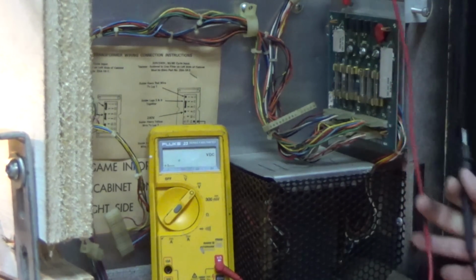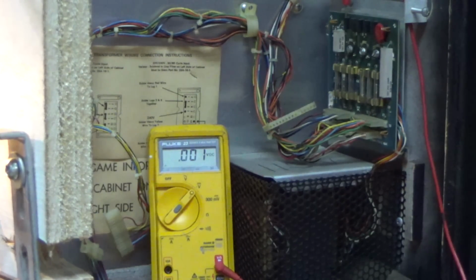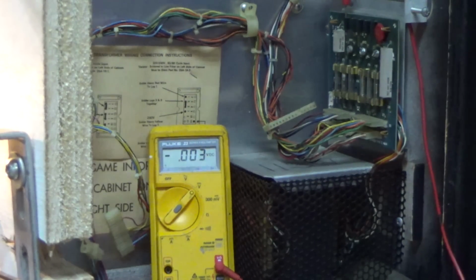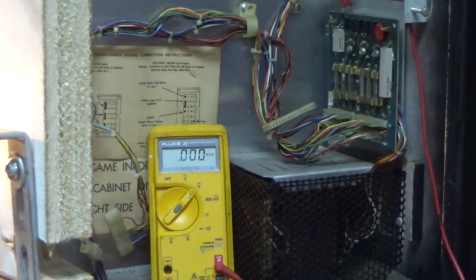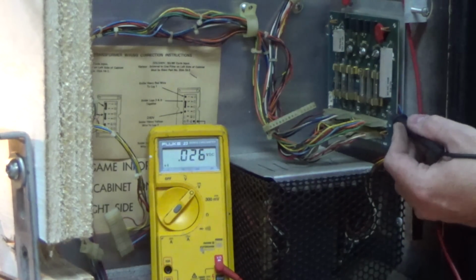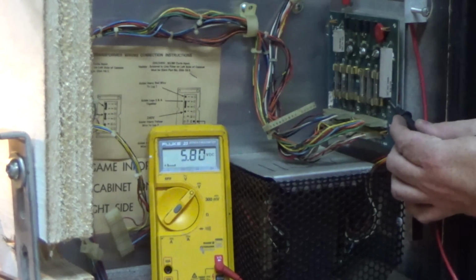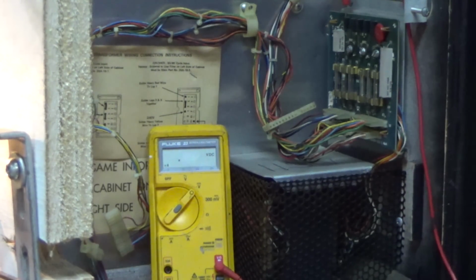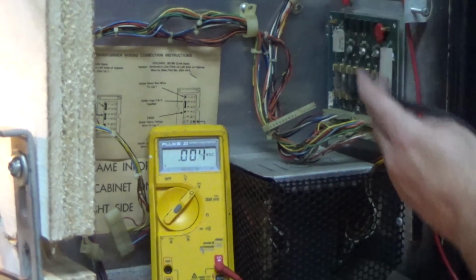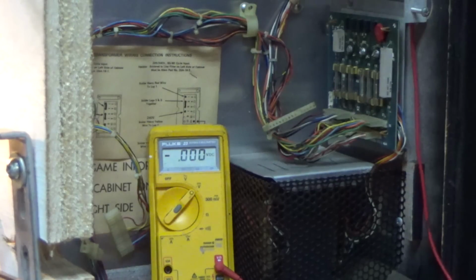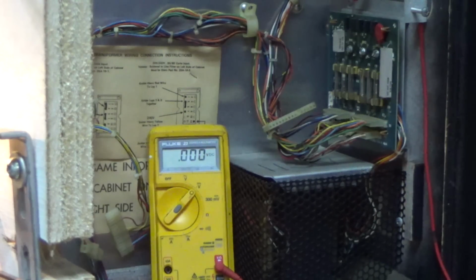Oh, I should look in the schematics to see if that's correct, shouldn't I? Luckily I have them right here. TP1 on this, it says 5.4 on the schematic. In reality, we're getting 5.8. Now what is that? That's that extra wall line voltage that I was talking about. Okay, so that's that one. Test point 1 is good. You don't need these to be dead on the money, you just need them to be in the ballpark.